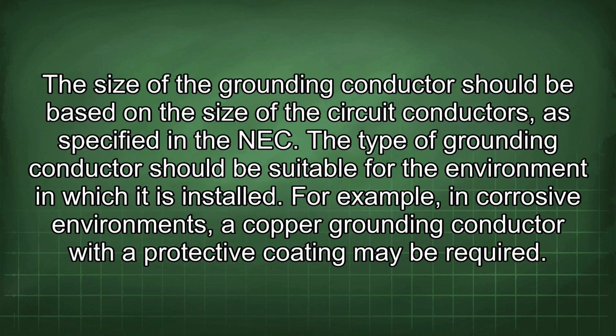The size of the grounding conductor should be based on the size of the circuit conductors, as specified in the NEC. The type of grounding conductor should be suitable for the environment in which it is installed. For example, in corrosive environments, a copper grounding conductor with a protective coating may be required.